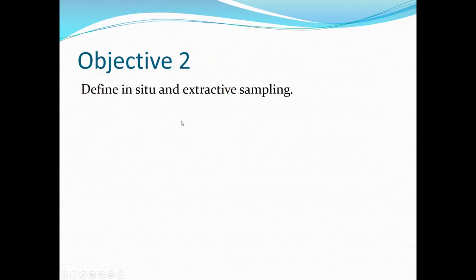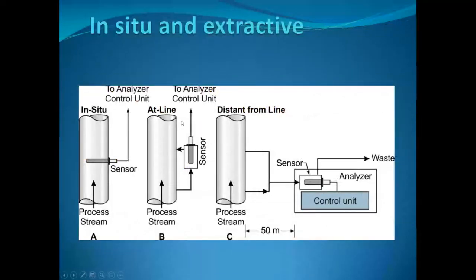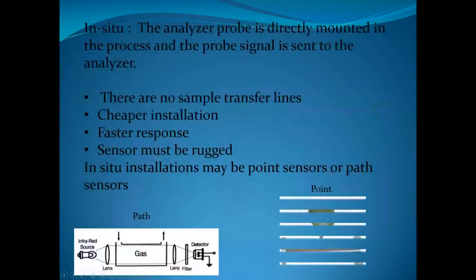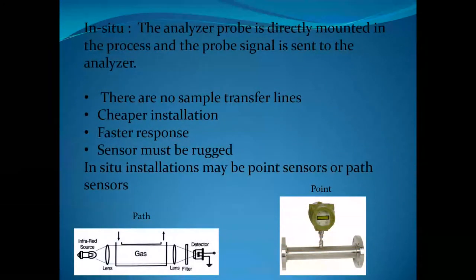For in-situ or in-line sampling, the sensor is in the process itself. For extractive sampling, the sample is pulled out and sent to a nearby sensor in a fast loop style, or transported some distance to a remote sensor. The two extractive types are considered at-line and distance-from-line respectively.